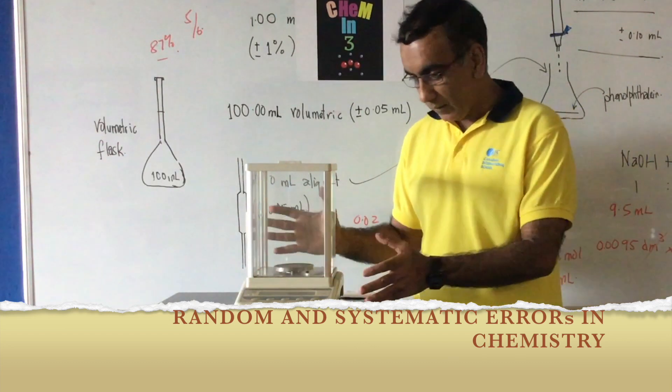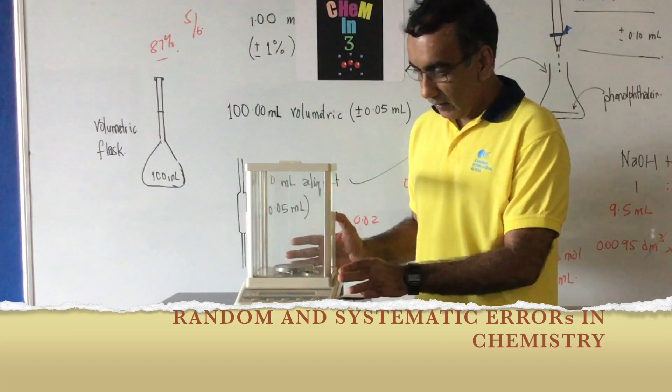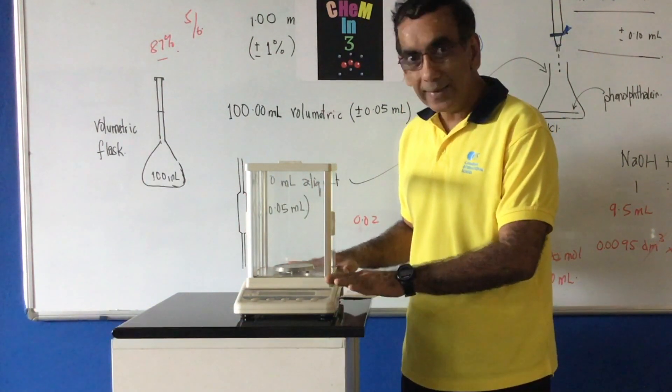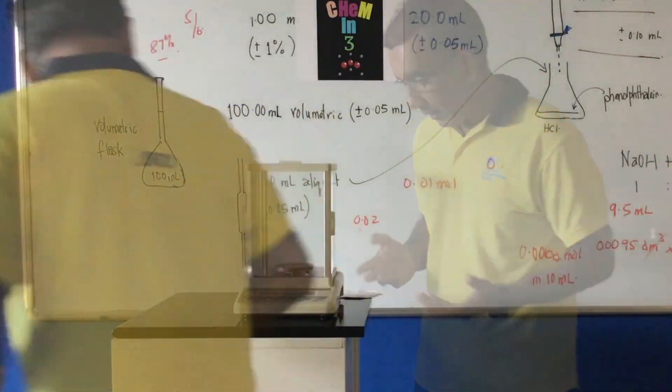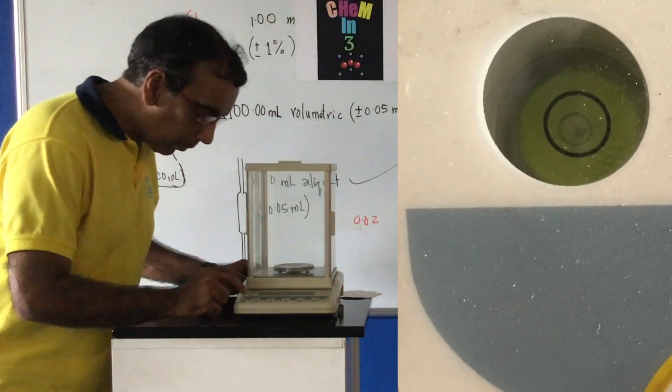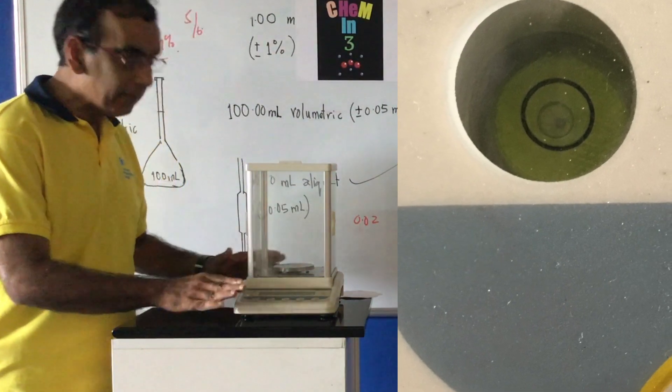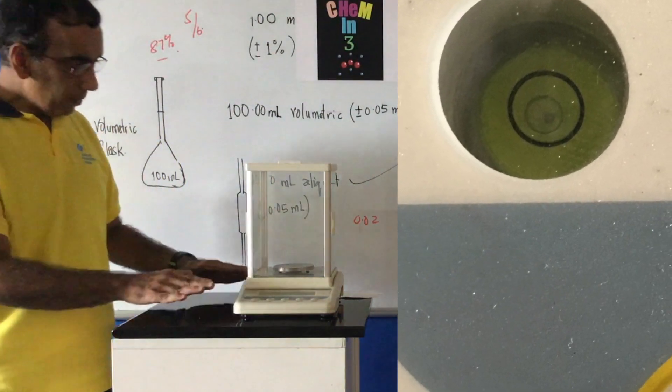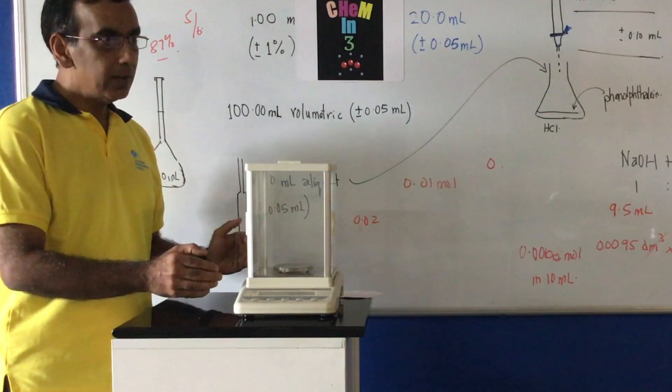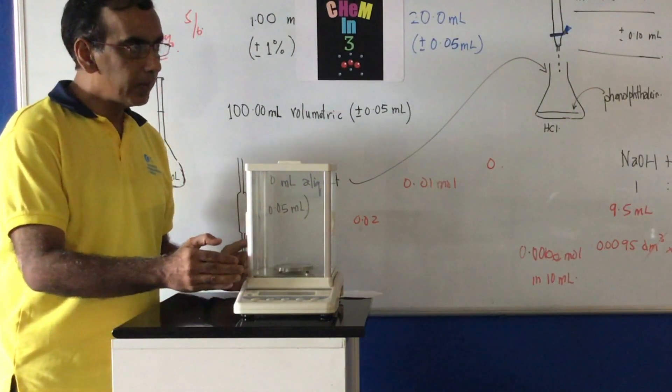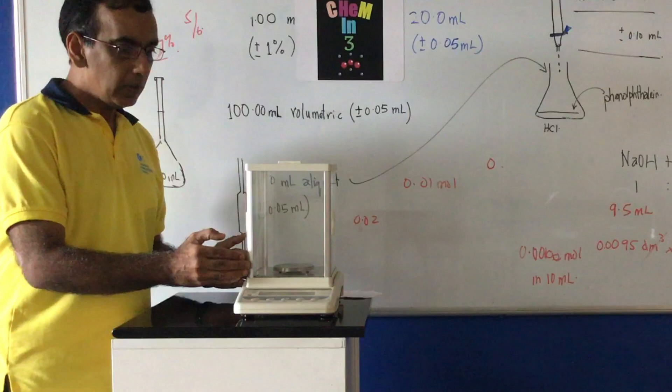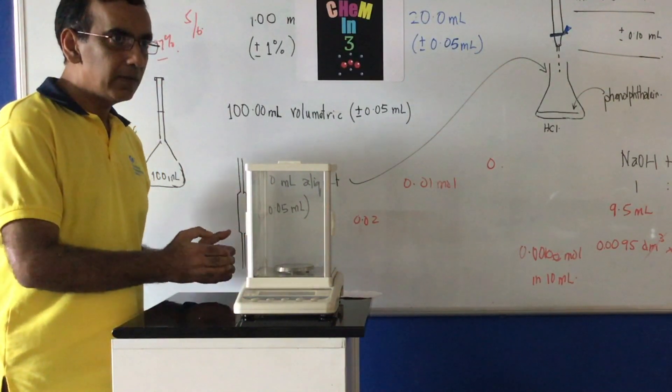Before I begin to use this balance, it's important that I ensure that it's properly leveled on the surface. The balance does come with a tiny bubble in here that allows me to know if it's level on the surface. If the balance is not leveled, then this can lead all of my readings to be off by a particular factor.